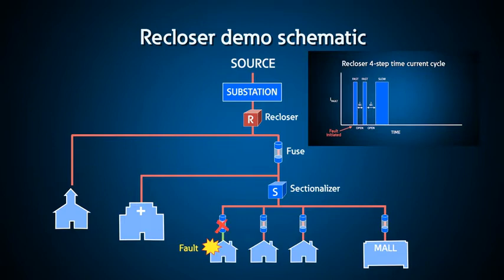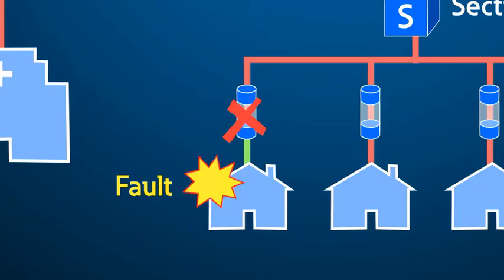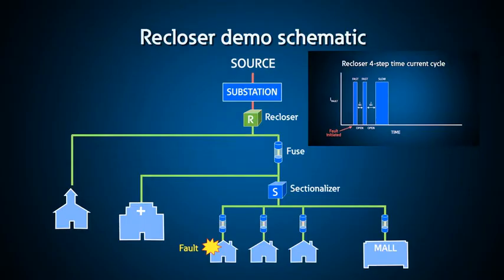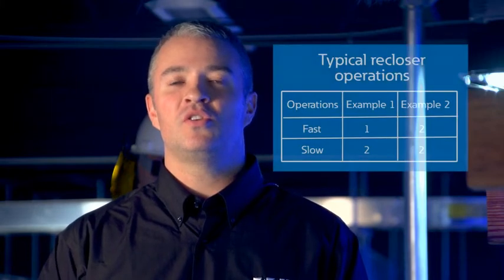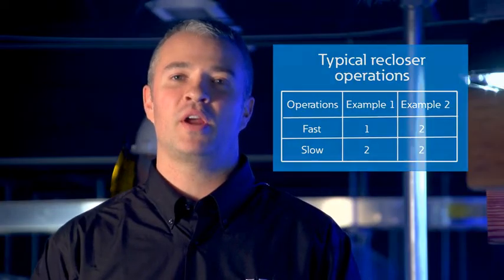If a downstream fuse blows, power is restored and the rest of the system returns to normal. Only the feeder downstream of the fuse is out of service. If the re-closer senses the fault during a subsequent fourth attempt to clear the fault and no downstream device has cleared the fault, the re-closer locks out and requires manual intervention as there is a permanent fault on the system. The combination of fast and slow operations is programmable and selected based on utility standards — for example, some utilities use one fast and two slow, but the most common combination is two fast and two slow operations.